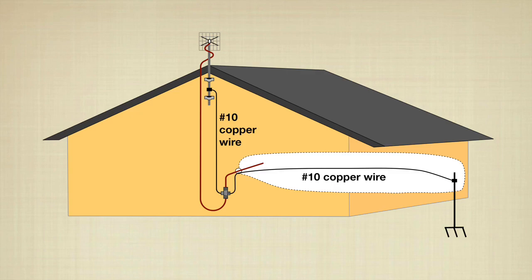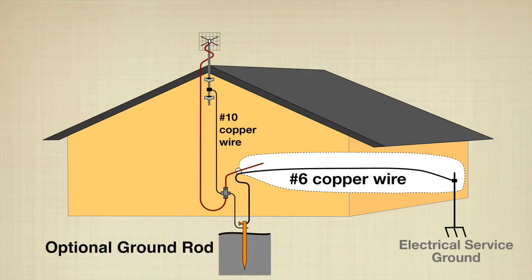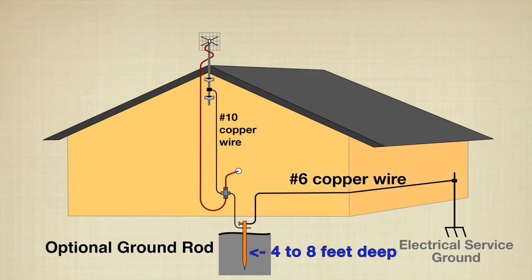Sometimes when the coax ground block is a long distance from the electrical service ground, an optional ground rod can be installed near the ground block. In this case, number six copper wire should be used between the ground rod and service ground. Some codes require the ground rod be at least eight feet deep. Others require four feet.